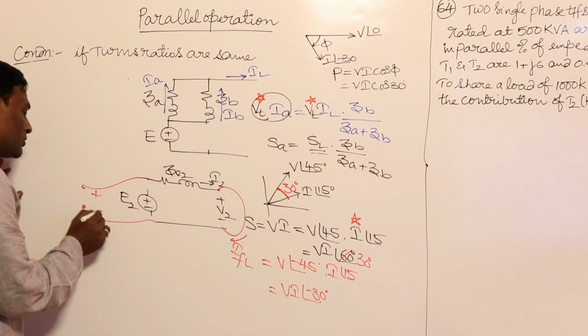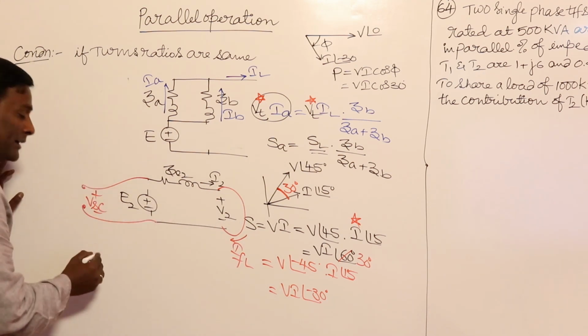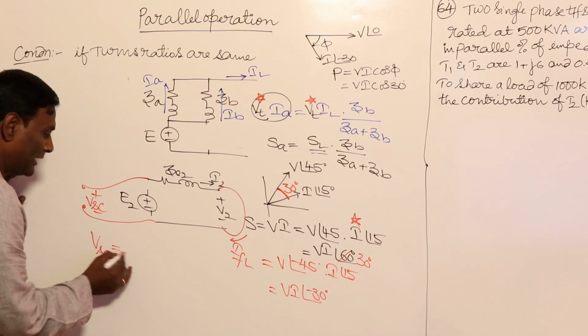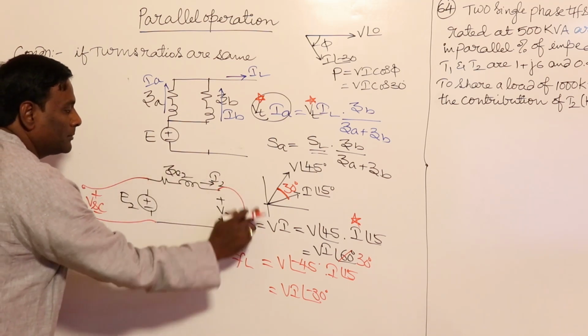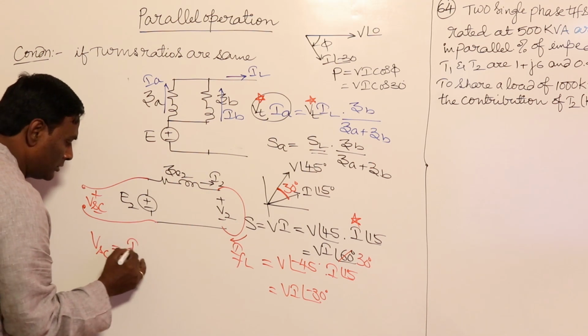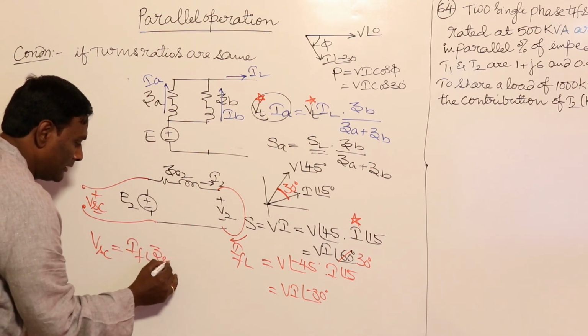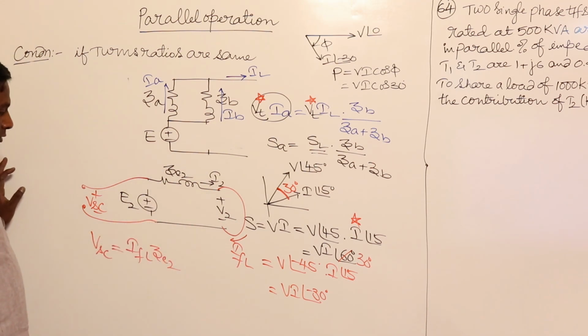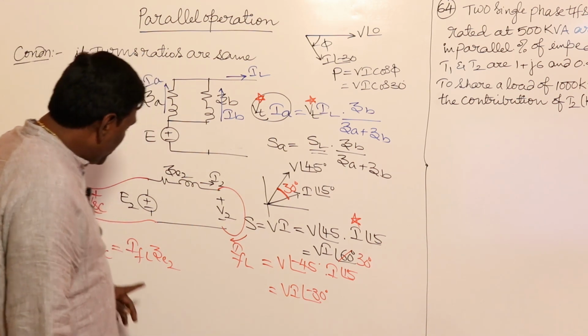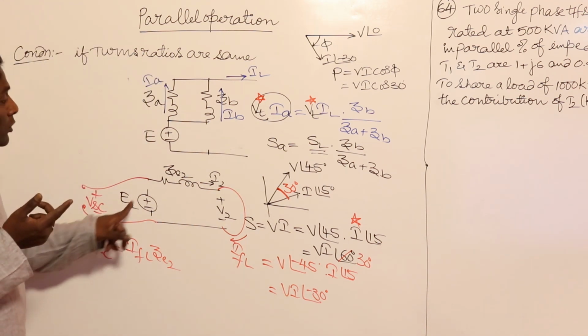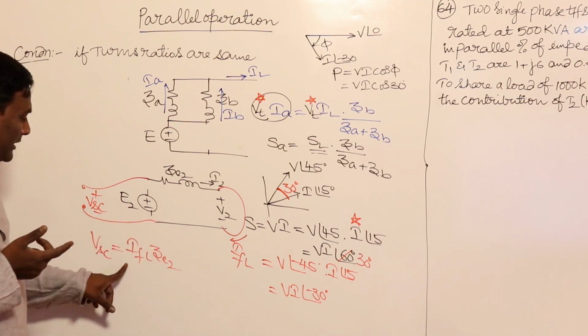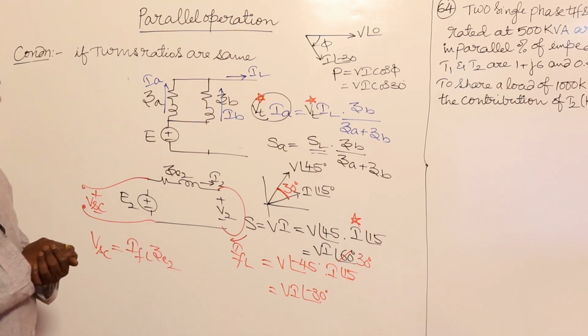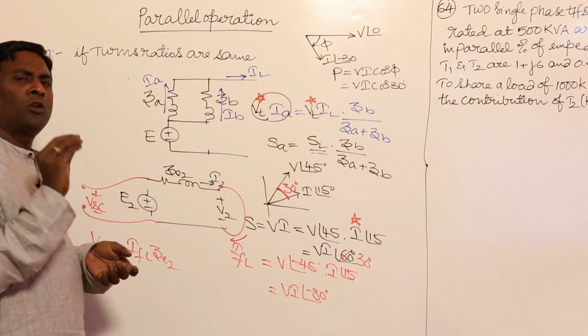How much should be the short circuit voltage to be supplied? Short circuit voltage to be supplied equals full load current multiplied by ZE2. So IFL multiplied by ZE2. Okay. So the short circuit voltage to be supplied to circulate full load current in this is going to be IFL ZE2.